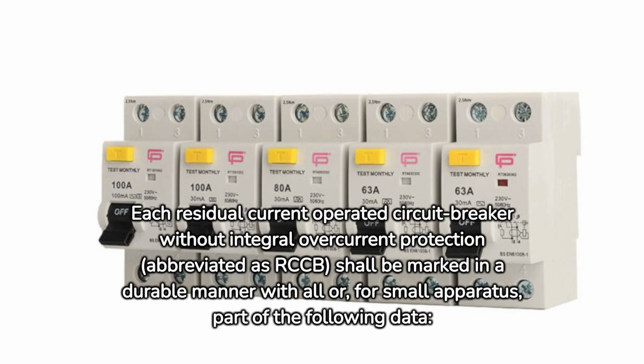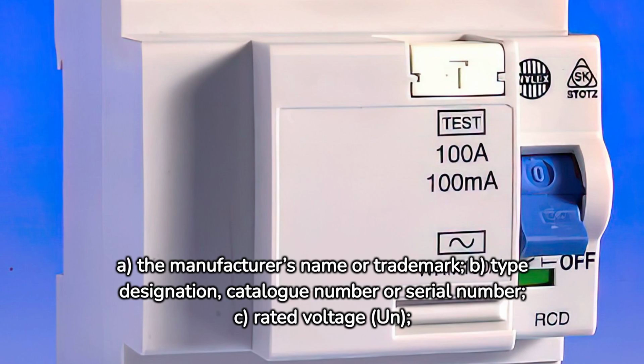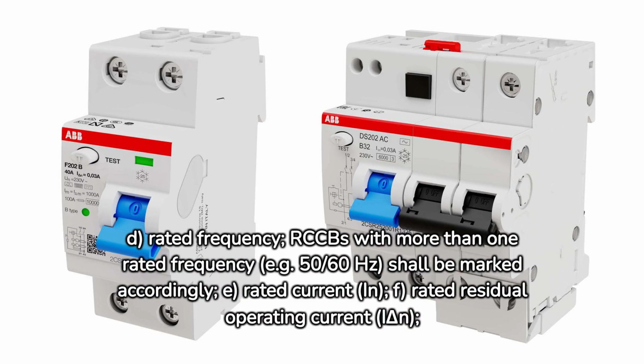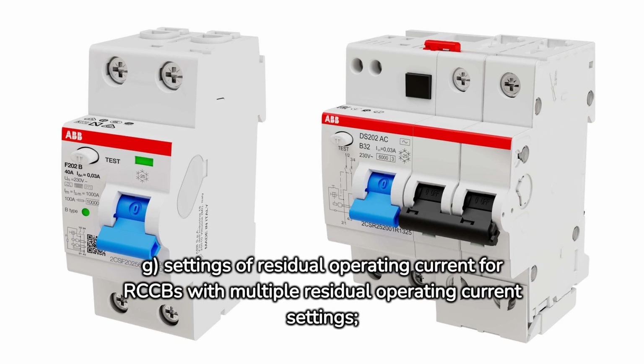Each residual current operated circuit breaker without integral overcurrent protection, abbreviated as RCCB, shall be marked in a durable manner with all or, for small apparatus, part of the following data. A. The manufacturer's name or trademark. B. Type designation, catalog number or serial number. C. Rated voltage, Un. D. Rated frequency; RCCBs with more than one rated frequency, e.g. 50/60 Hz, shall be marked accordingly. E. Rated current, In. F. Rated residual operating current, IΔn.